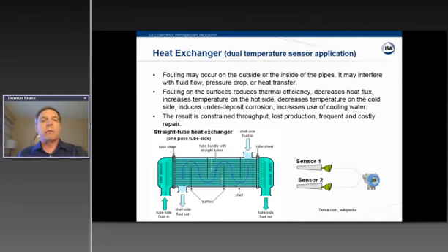So an application for measuring temperature in a heat exchanger is trying to detect fouling. Fouling might occur on the outside of those tubes, because in our polyethylene example the cooling water was running on the outside of the tubes, and that could result in scaling on the outside, or fouling can occur on the inside of the tubes. If the fouling occurs on the inside of the tubes, that'll create a pressure drop across the heat exchanger. It's going to restrict the fluid flow, and of course it's going to affect heat transfer. So that's going to result in reduced thermal efficiency.